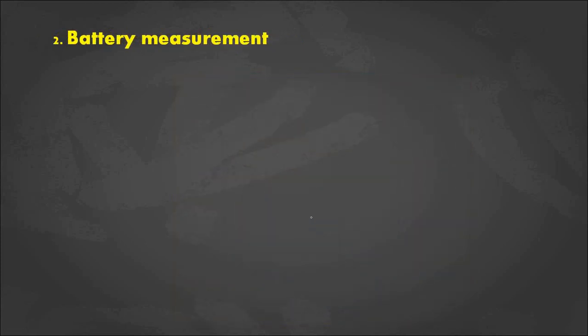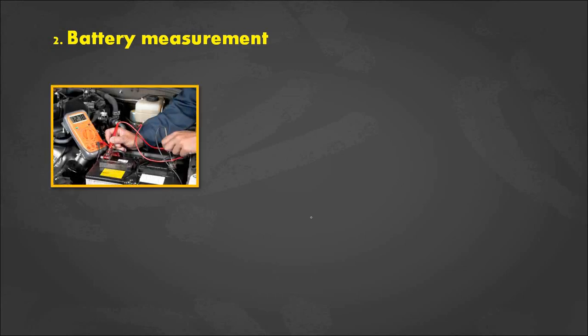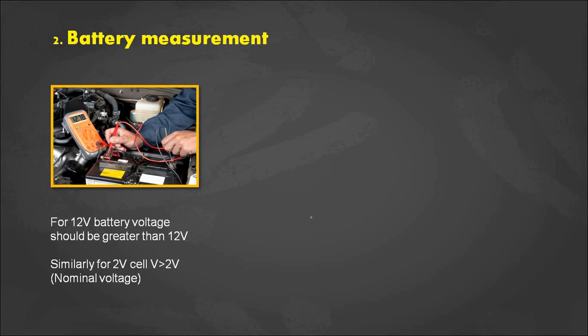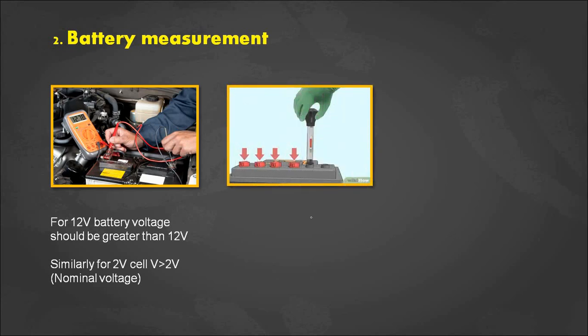The second one is the battery measurement. The battery measurement includes the measurement of battery voltage, specific gravity and temperature. By using a multimeter, we can measure the battery voltage. For a 12 volts battery, the battery voltage should be greater than 12 volts. If it is at 12 volts or below, we have to charge the battery. We have to maintain the battery greater than 12 volts. Similarly, for a battery bank, we will use 2-volt cells. We have to maintain the voltage greater than the nominal voltage, nothing but the 2 volts. This nominal voltage is given in the data sheet. While you are purchasing a battery, a data sheet is given. In the data sheet, the voltage levels, specific gravity levels and the temperature are given, so that you have to maintain them.